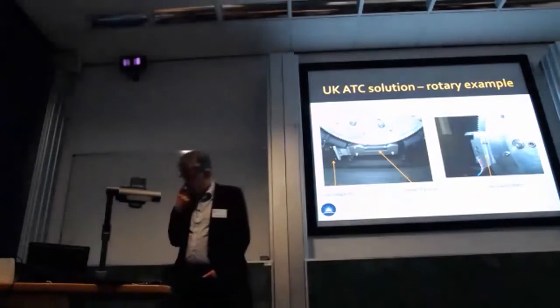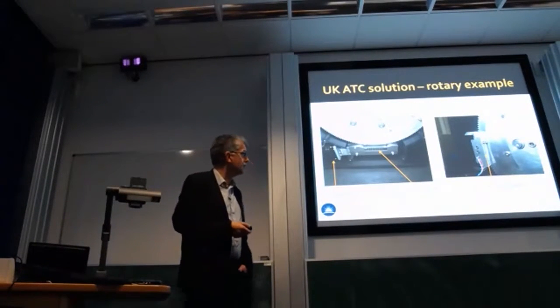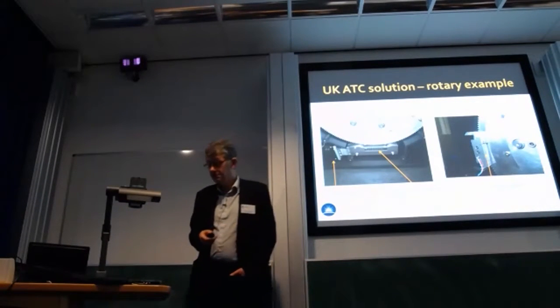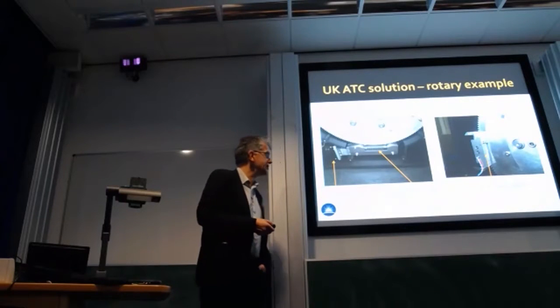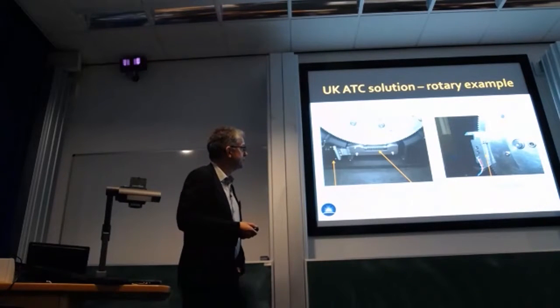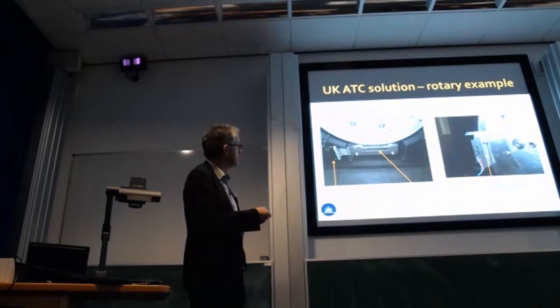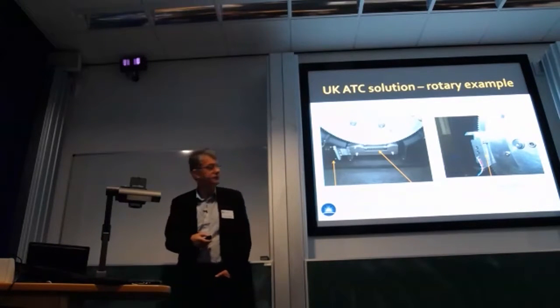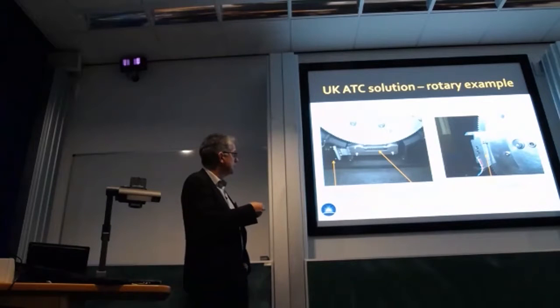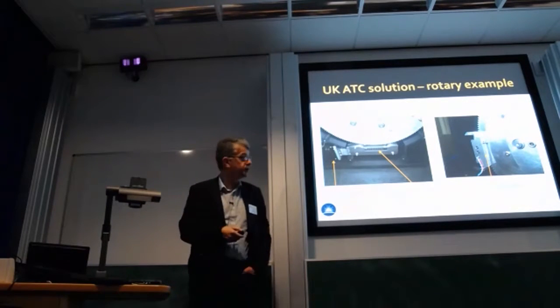And the way we've done it over maybe 20 or 30 years, we've evolved a sort of standard mechanism and position sensing philosophy, which is kind of simple. We use an aluminium wheel with a Vespel plastic worm with dry lubrication, and a stepper motor which is kept cold at the same temperature as the rest of it, so we don't have long shafts going outside the cryostat.